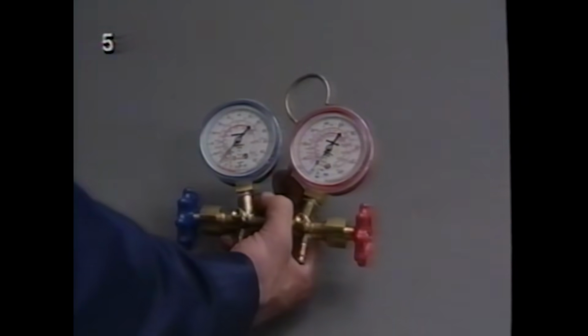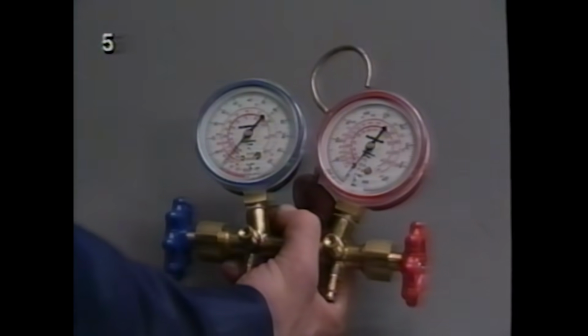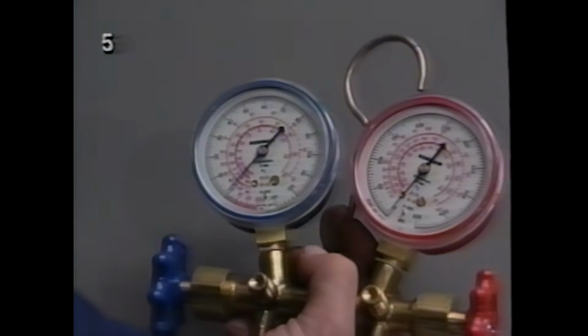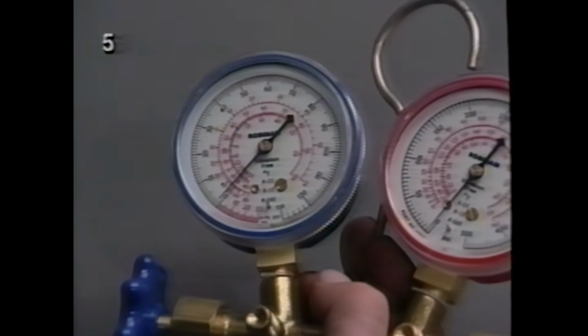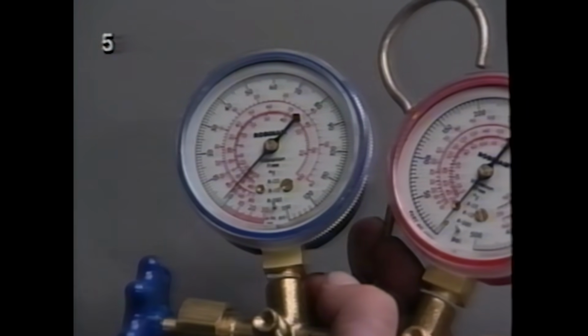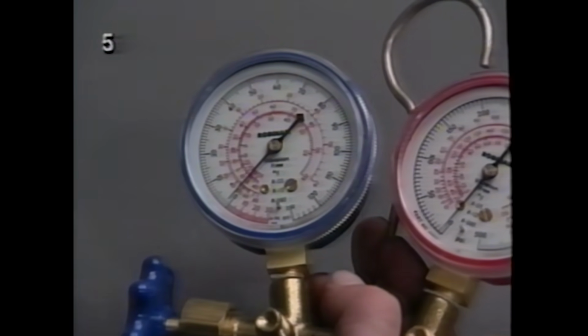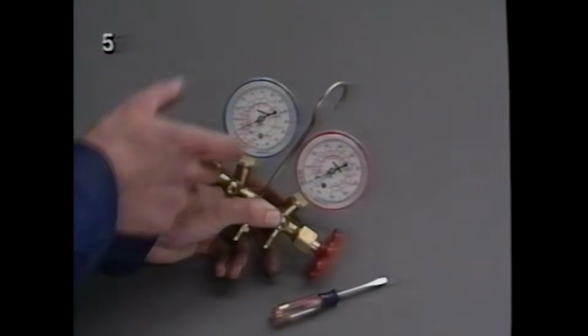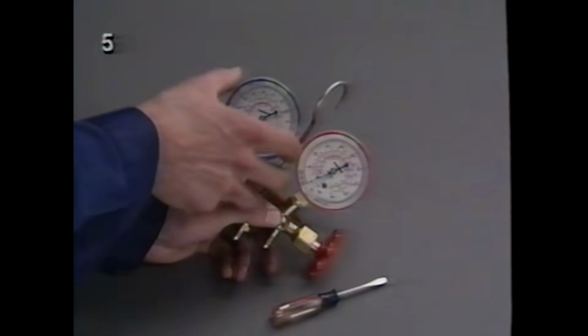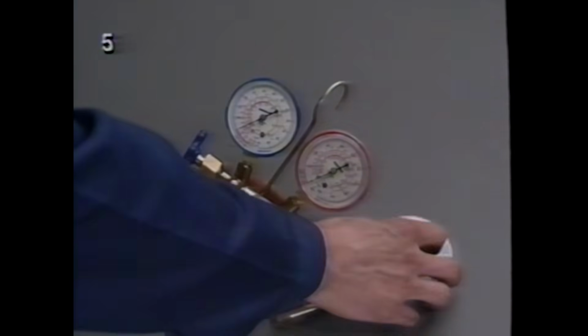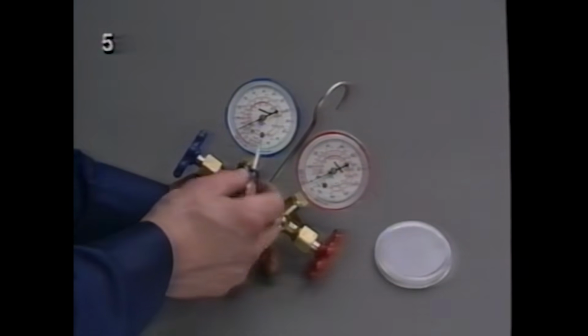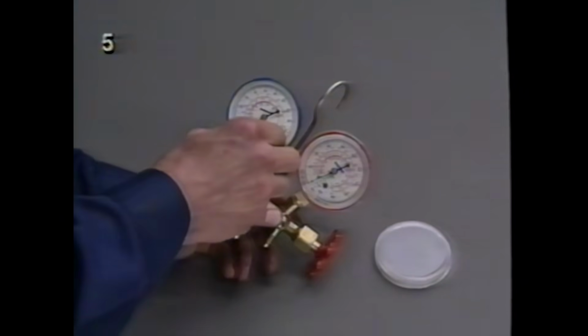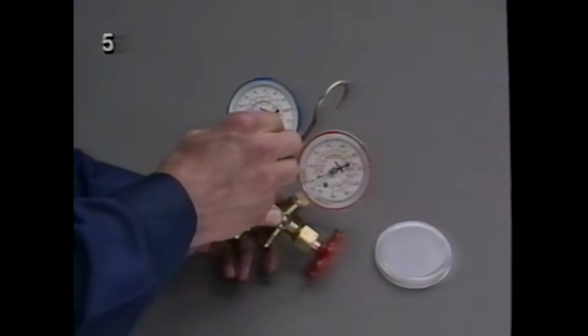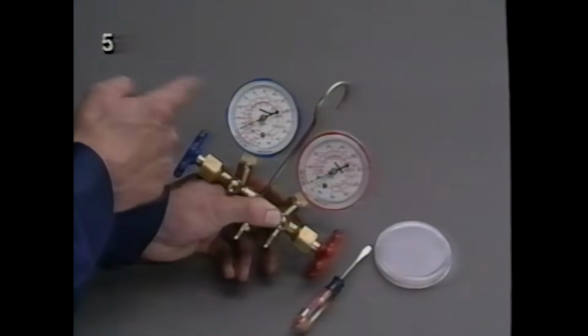The gauges have to be properly calibrated in order not to overcharge the system. With the low pressure gauge disconnected from the refrigerant system, the needle should be centered at 0. Tap it a couple of times so you're sure it isn't sticking. You can calibrate a gauge this way if you have to. Take off the cover and turn the adjusting screw until the indicator is centered on 0. Then give it another tap to make sure it doesn't stick and put the cover back on.